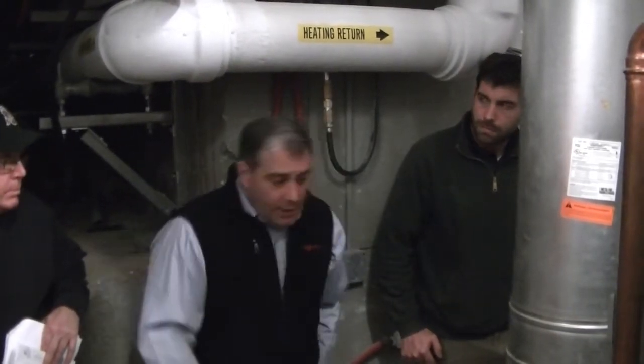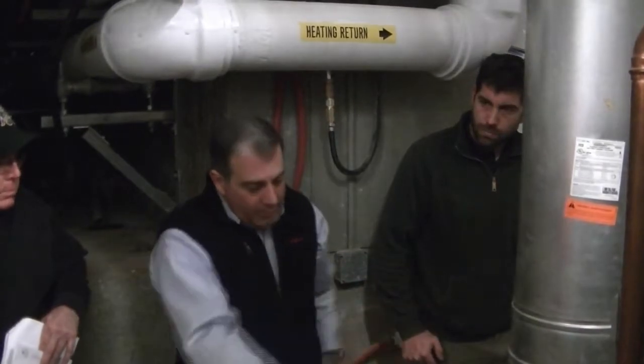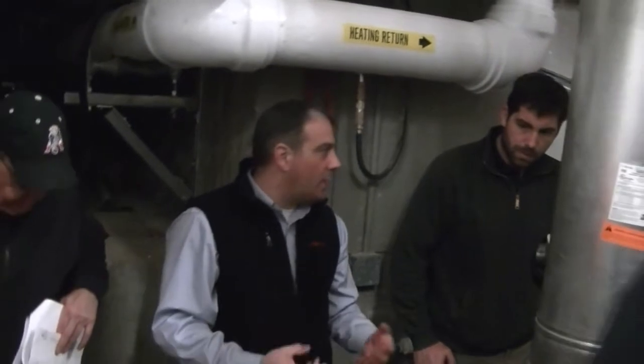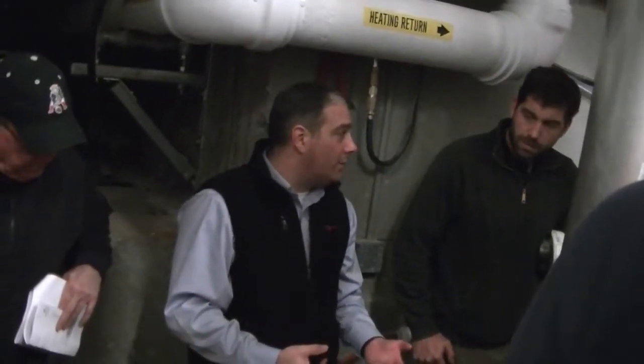So in the Viessmann preventative maintenance literature, it says to check the pH of the condensate. That's not so important on the boiler side, but you want to check it coming out of this condensate neutralizer, especially if you have cast iron soil pipe in the building for drainage. Because if you have a low pH going into that cast iron drainage system, you'll start to rot away the cast iron over time.